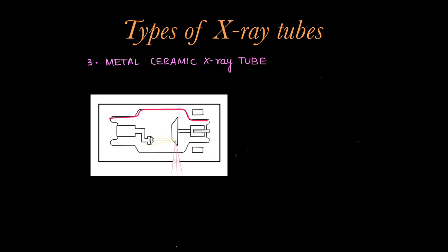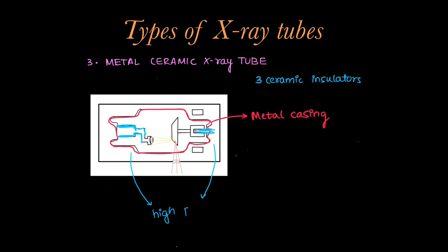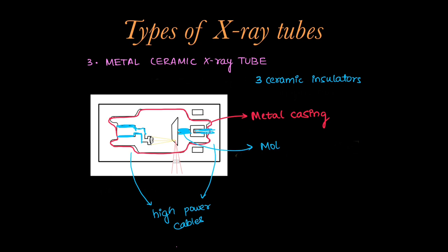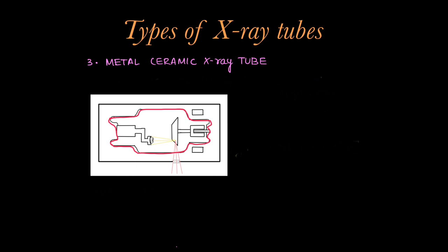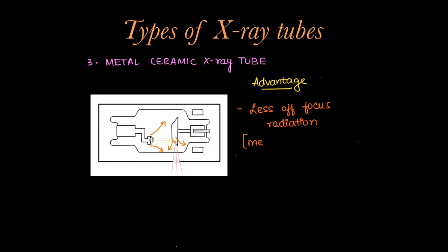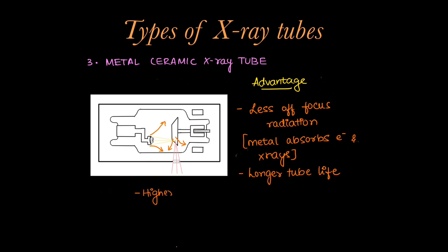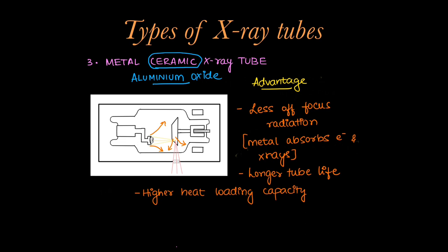The next type is the metal or ceramic x-ray tube, which has a metal housing instead of a glass housing. It has three ceramic insulators: one at the cathode, one at the anode for lining the high power cables, and one ceramic coating at the molybdenum stem. This has a better shelf life than glass envelopes. There is less off-focus radiation in metal envelopes because metal absorbs excessive electrons or x-rays that are off-focus. It has a longer tube life and higher heat loading capacity. The ceramic is made of aluminium oxide.